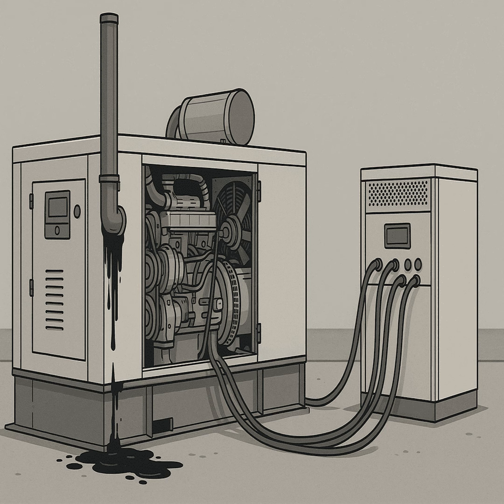Okay, so that leads us right into the causes. If diesel needs high temperatures, I'm guessing the main cause involves not reaching those temperatures. You've got it. The number one culprit, hands down, is low load operation. Running it too gently, basically.